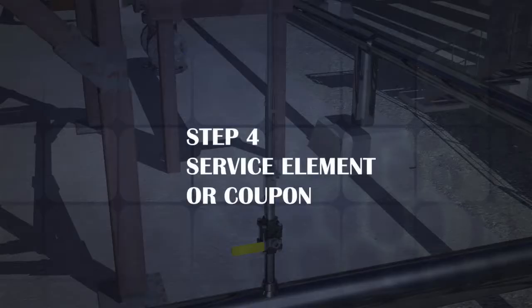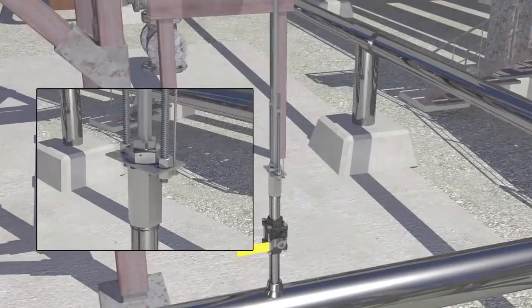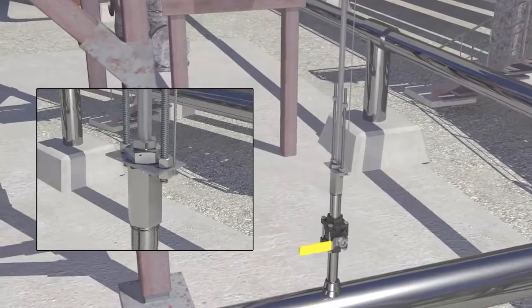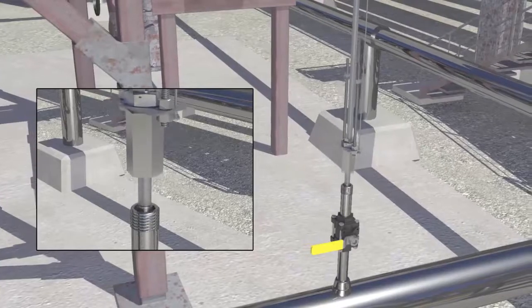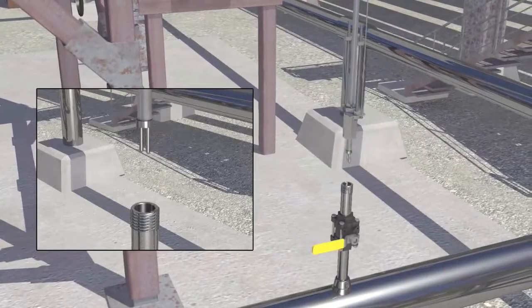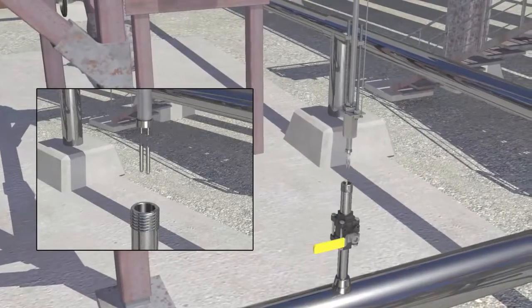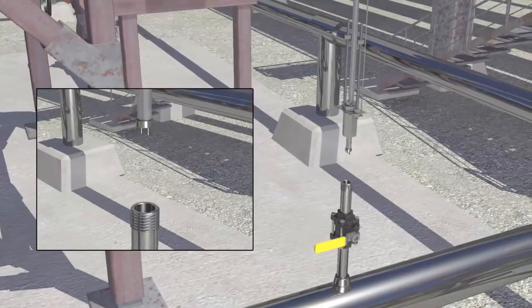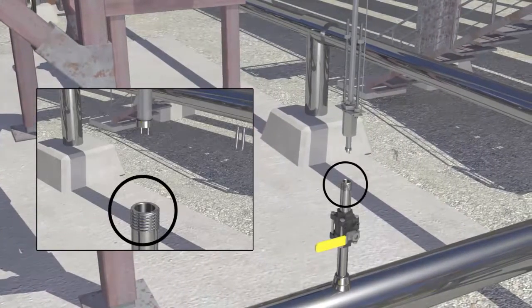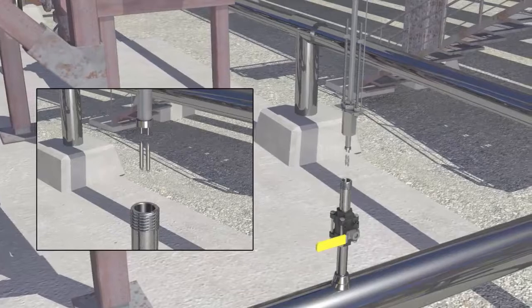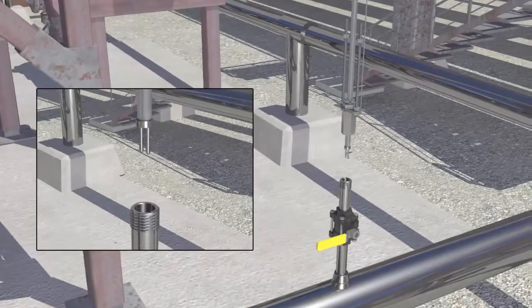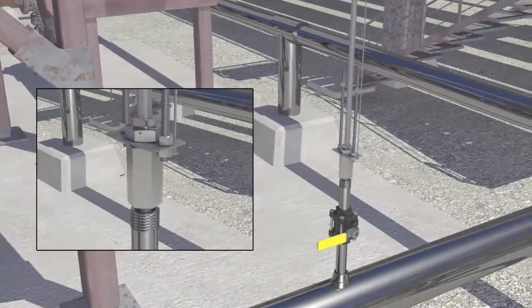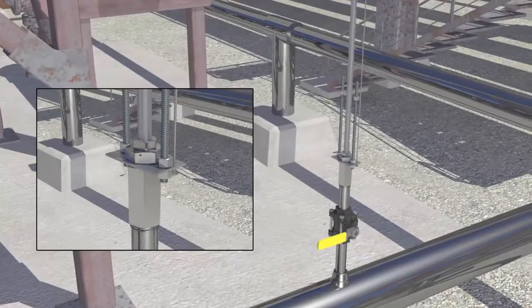Step 4. Service element or coupon. Remove the stuffing box assembly from the access valve outlet nipple and remove the probe assembly to expose the element or coupons. Replace the element or coupons as necessary. Apply thread sealing compound or PTFE tape to the threads of the outlet nipple. Mount the stuffing box assembly onto the access valve outlet nipple and tighten to 2 3/4 to 3 1/4 full turn past hand tight.